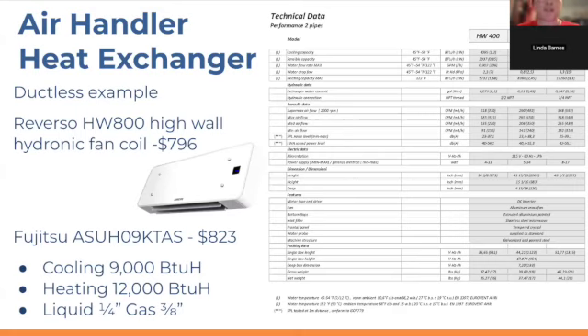I used to think that the price difference between the hydronic coil and the air refrigerant coil would be much more expensive on the hydronic coil side, but turns out, not really. But again, the pipe size is pretty significantly different.